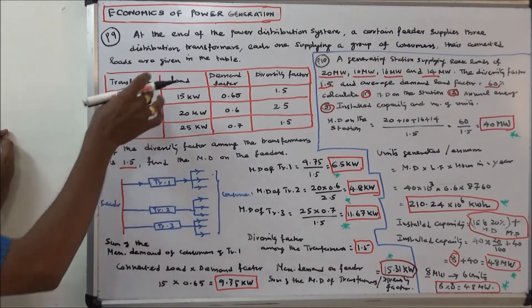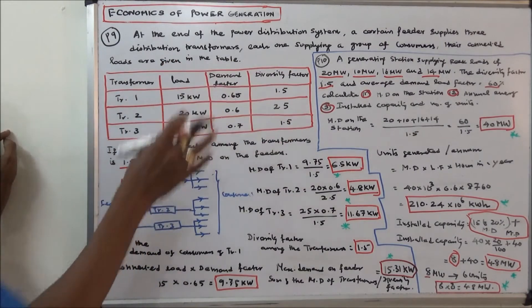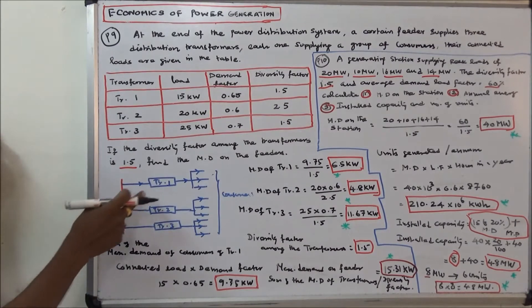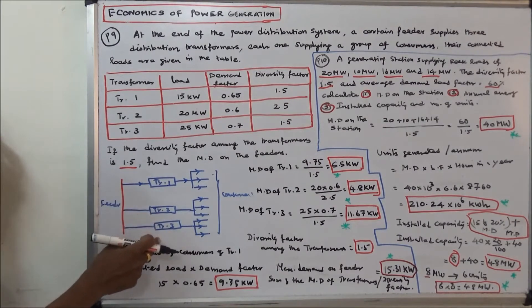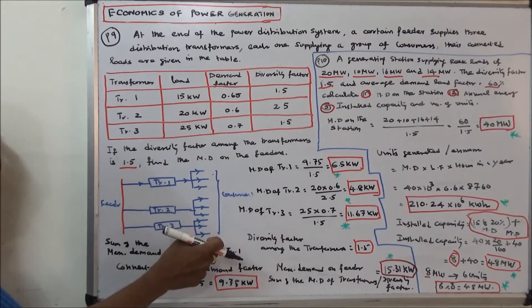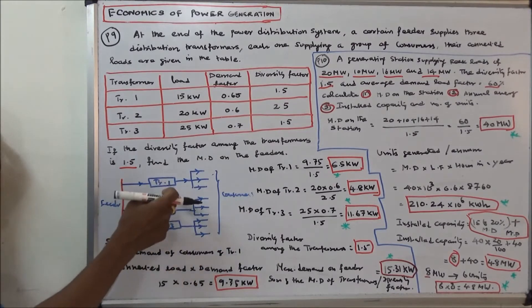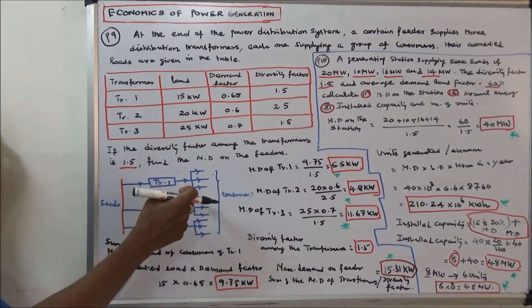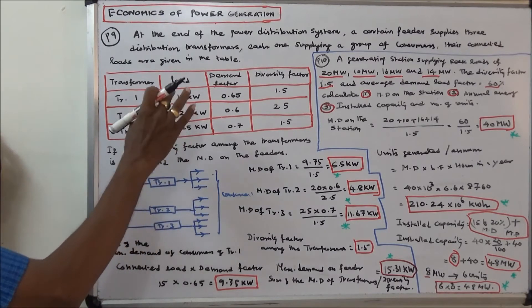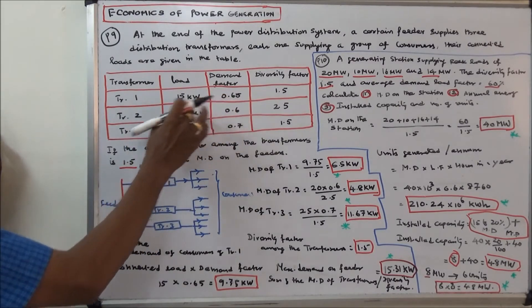The transformer load is given, the demand factor is given, and the diversity factor is given. This is the feeder supplying transformer one, transformer two, and transformer three — these are all the consumers. First, we calculate the sum of the maximum demand of consumers of transformer one, which is equal to connected load multiplied by demand factor.